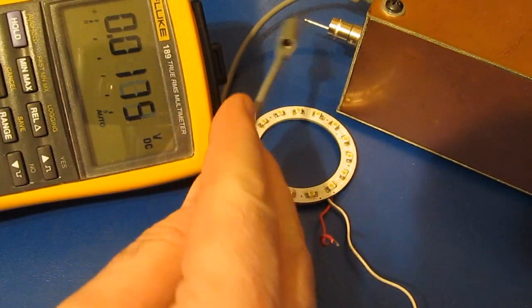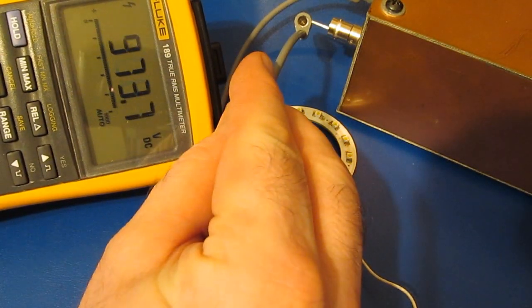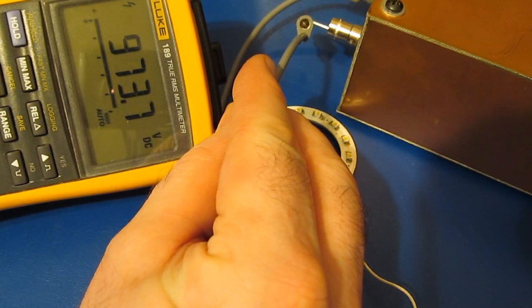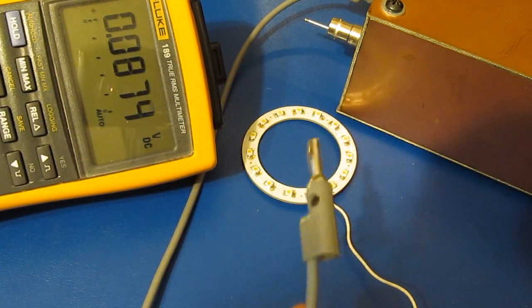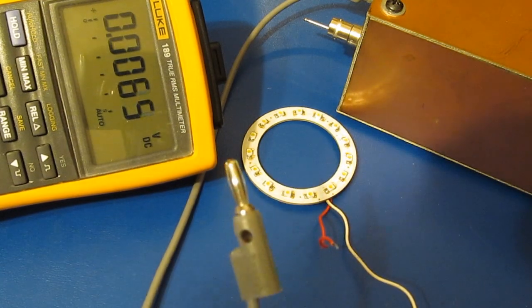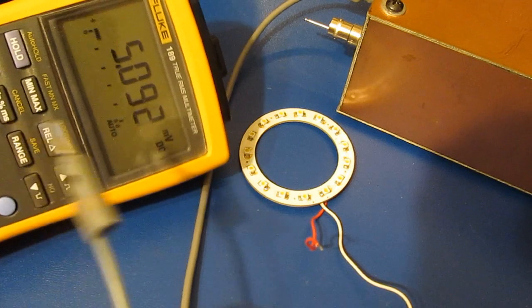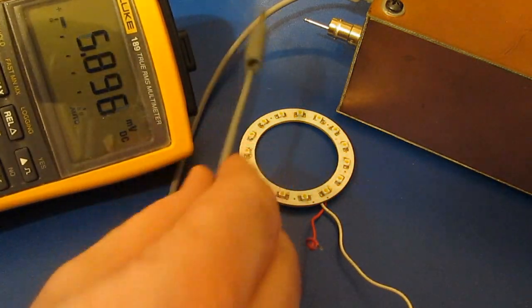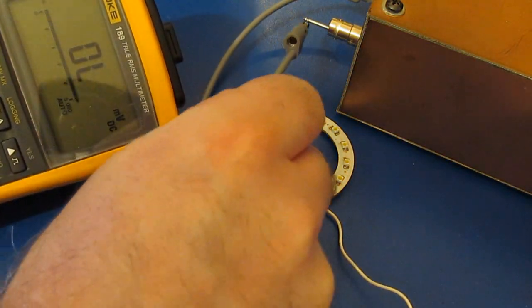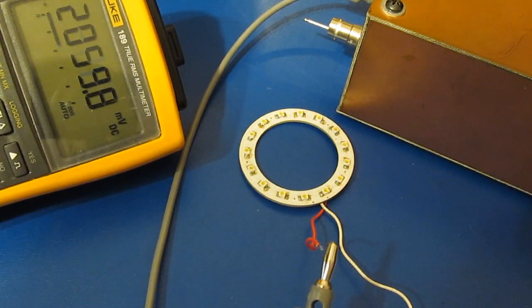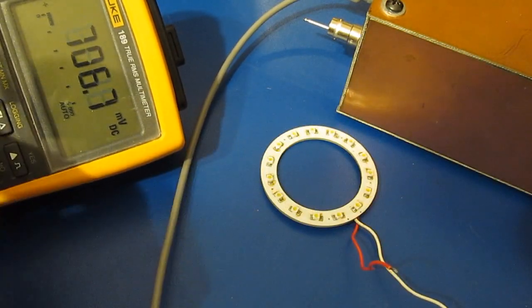And just to show you that this is live. There you go, 973 volts. And you can see nothing. Same thing if I put it in the millivolts DC mode. We shouldn't get anything. It's going to engage the clamp. But you can see no transient.